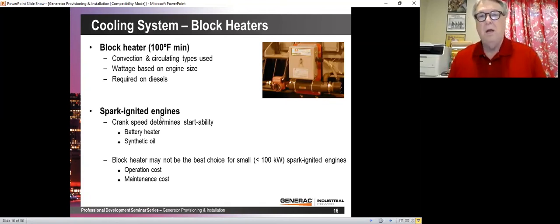Block heaters. Block heaters are very important for diesel engines. The most important thing you can do is make sure that engine is warm, because they are compression ignited, not spark ignited. So typically we use a block heater that is a circulating type where you just heat the fluid, the coolant, and the coolant naturally flows by convection up and through the generator. And that's a very slow heating process, but it works just fine. When you get into some very large generators, then you may have to have a pump on there or even multiple heaters. Typically, we'd like to keep the engine block at 100 degrees. And so that's one of the things you should check daily when you go out and check your generator, is to see if it's warm.